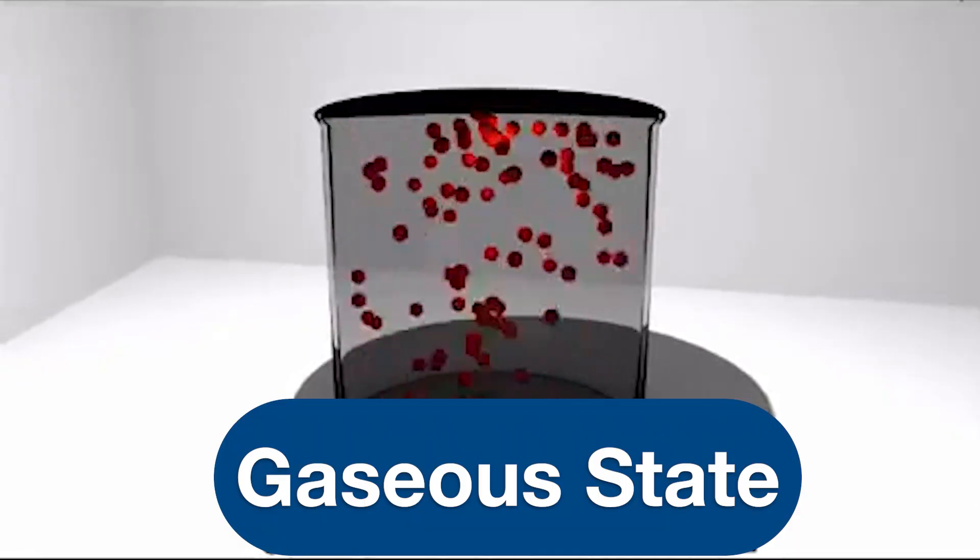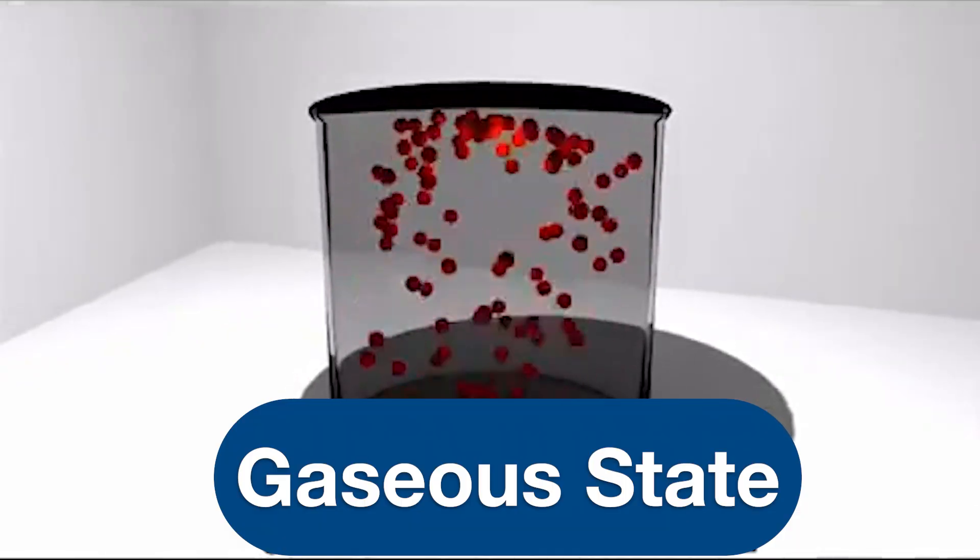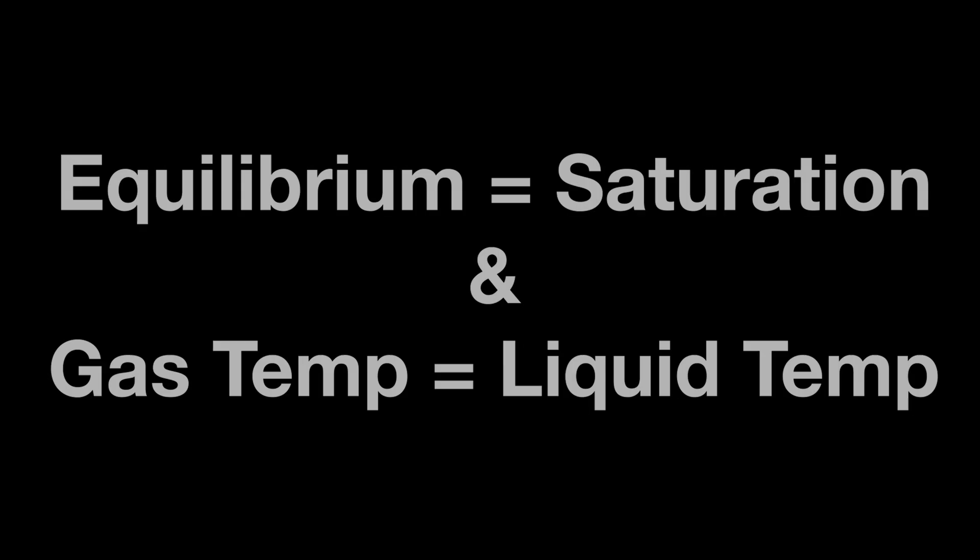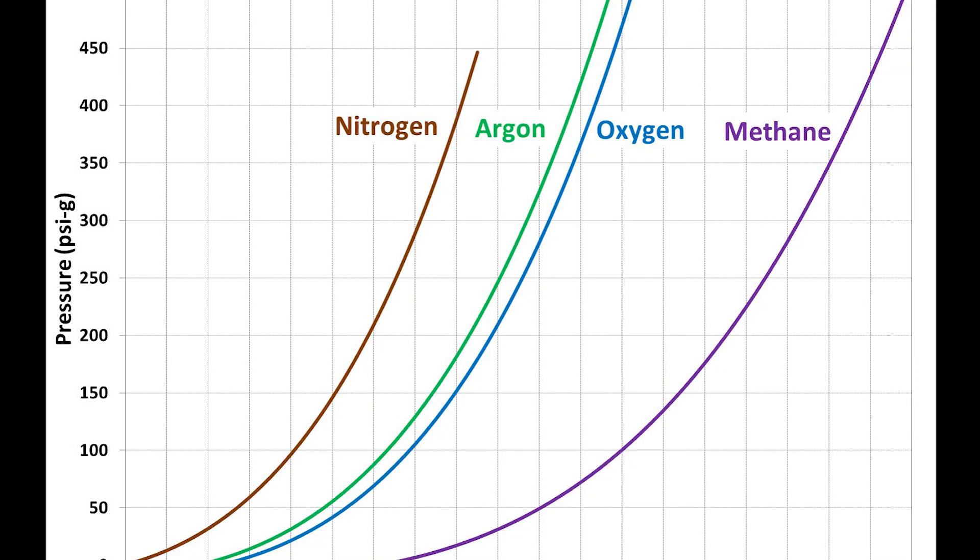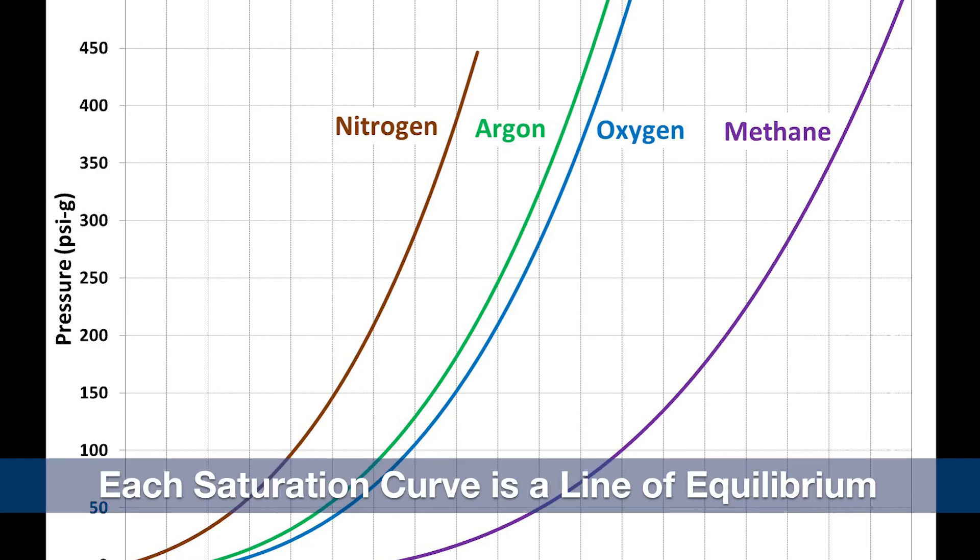An equilibrium or saturated energy state has a specific pressure and temperature associated with it. This is called a saturation pressure or saturation temperature. Although assessing the saturation state can be accomplished by measuring temperature, the most convenient property for measurement is typically the fluid pressure.